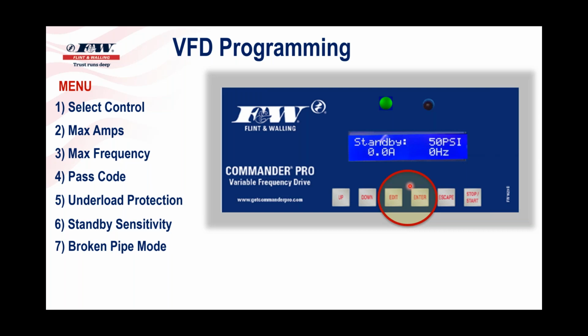I'll tell you a quick little story on this broken pipe mode. Back years ago, we were in field test, and we had a distributor up here in northern Indiana that had an outside salesman that was going to help us with our field test of these drives, and so we upgraded his home submersible to include a variable frequency drive. And the only thing we asked is to be able to come in periodically to just kind of do a check and balance and monitor it and see how things are going.